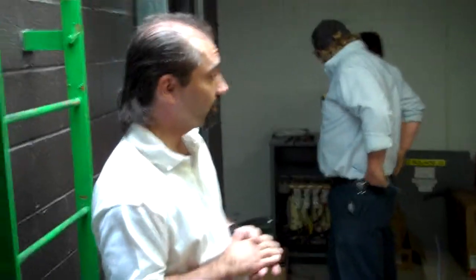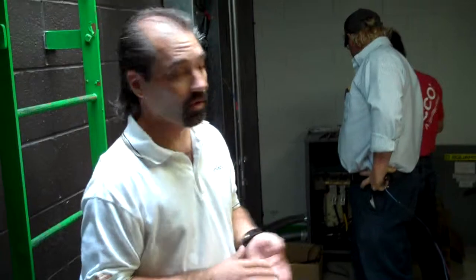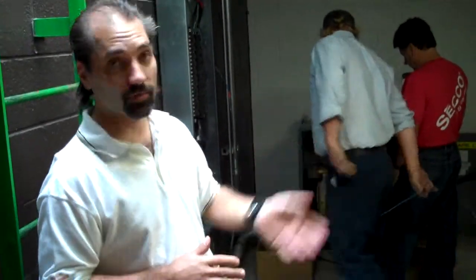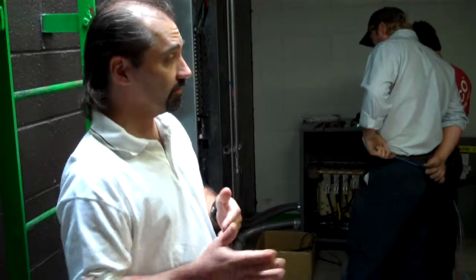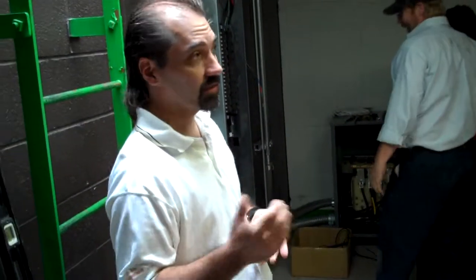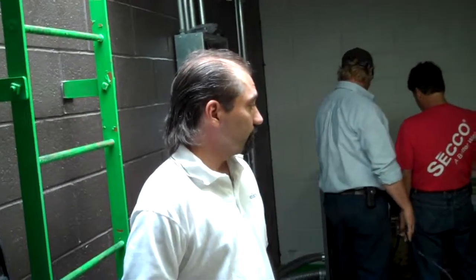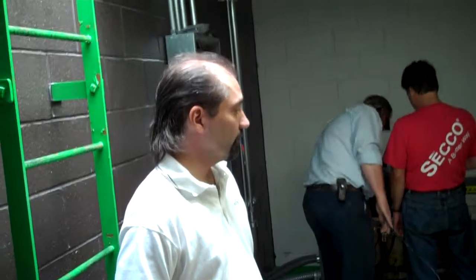The other real trick with this, and you touched on not having to run ductwork, is the time and labor savings in running the copper piping versus trying to get ductwork throughout the entire school. That was huge on this project. Now we only essentially had to get 2 trunks down through the center corridor in the first floor and the second floor, and essentially 3 refrigerant piping systems. So it was a lot faster and a lot quicker to get the refrigerant piping in versus hanging all that ductwork. And not to mention the indoor air quality issues a lot of schools have with mold growth and all the issues surrounding fresh air and clean air for students. So we'll expect to see the grade point averages increase on all the kids. That's what we're hoping for.